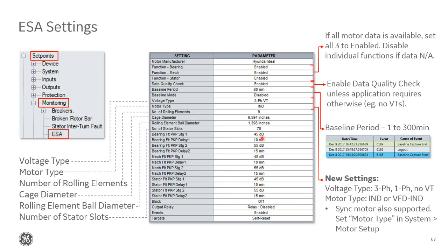So generally, we would recommend that you leave the settings at the default 45 and 55 max change value dBs to start with. This is more on the conservative side. And then once you have this in service and you have some good data, you can go back and see what your typical values are and then adjust these down accordingly.